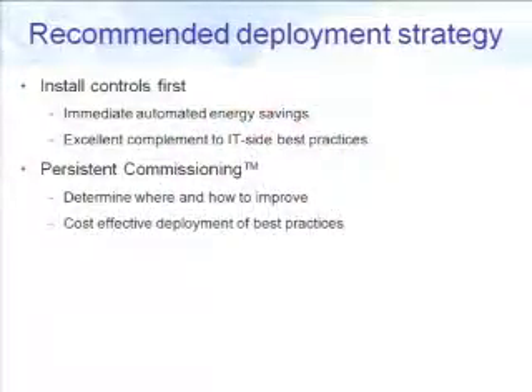I won't talk to this much because I'm sure you've had the same experience, that deploying these sensor networks adds a lot of value in helping you see where there are issues in your data center, and gives your facilities people an insight they've never had before. There's a huge value in that, and we recommend that first to our customers. Coupled with our system, you can get energy savings right away, and then really look at other best practices out there, especially around cooling, whether it's hot aisle or cold aisle containment, making sure all your holes are plugged in your under-floor air distribution, blanking panels, all this stuff. Having a system that gives you a lot of data is really a good first step, and it sounds like you guys are doing this.